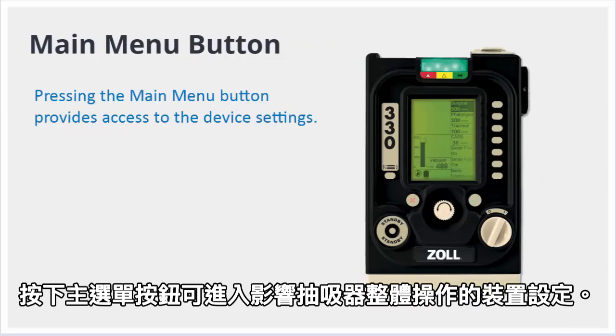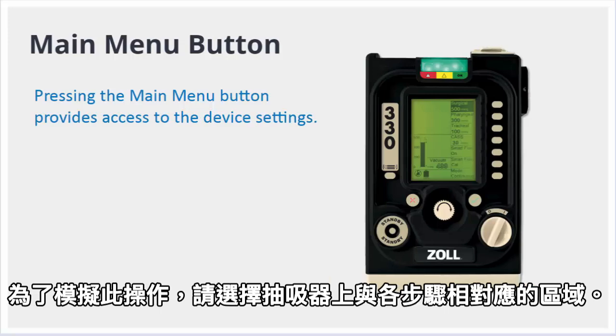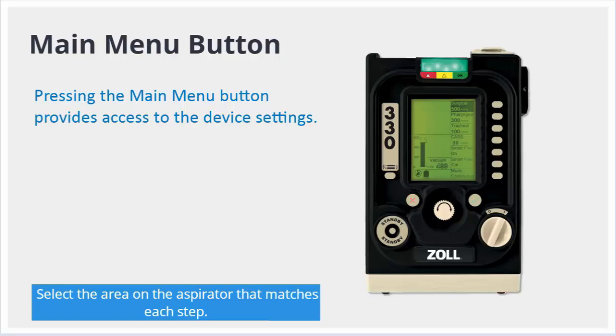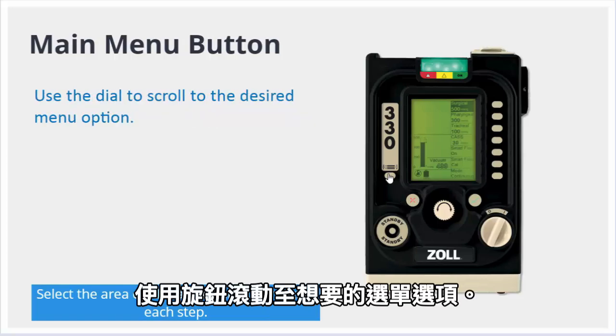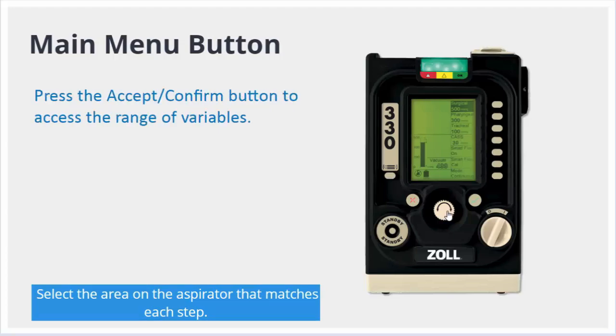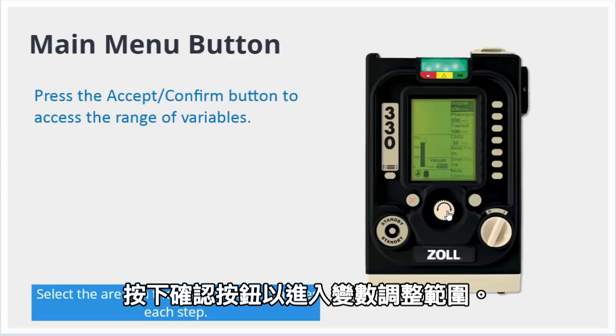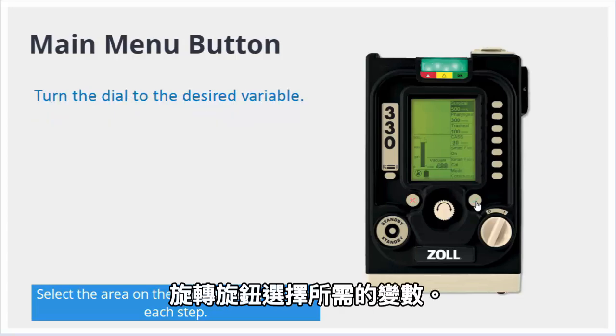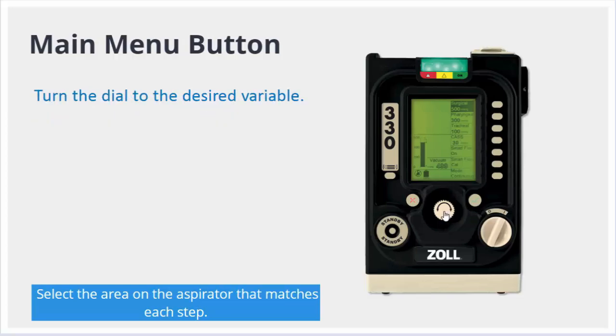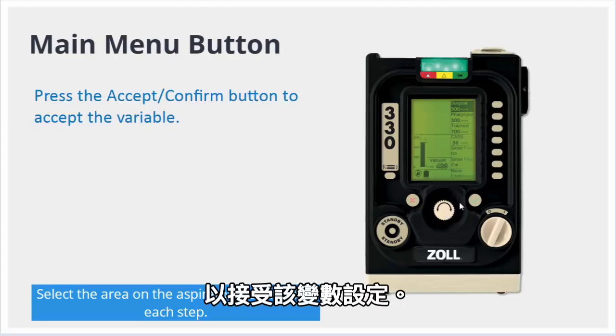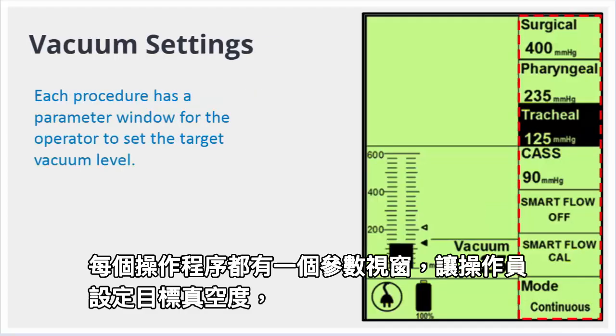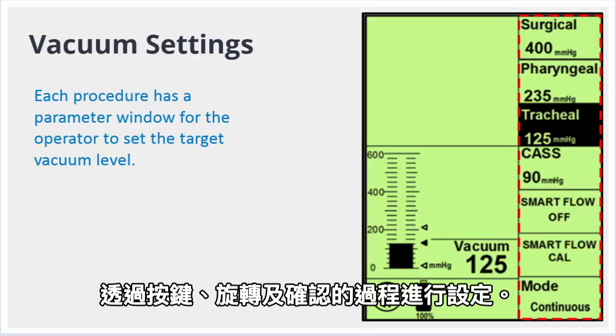Pressing the Main Menu button provides access to device settings that affect how the aspirator generally operates. To help simulate this process, select the area on the aspirator that matches each step. Use the dial to scroll to the desired menu option. Press the Accept Confirm button to access the range of variables. Turn the dial to the desired variable and press the Accept Confirm button to accept the variable. Each operation procedure has a parameter window for the operator to set the target vacuum level using the touch, turn, and confirm process.